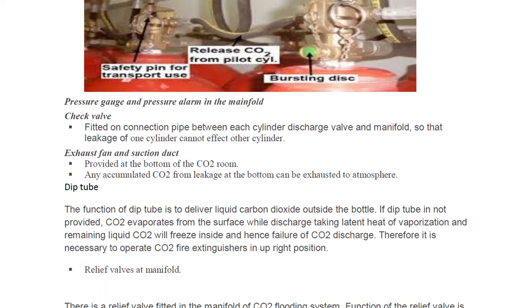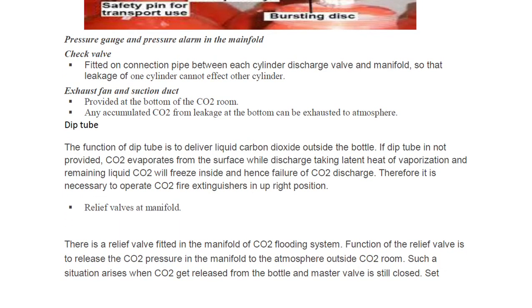We also have a dip tube. The function of a dip tube is to deliver liquid carbon dioxide outside the bottle. It is very important and necessary. If the dip tube is not provided, CO2 evaporates from the surface during discharge, taking the latent heat of vaporization, and the remaining liquid CO2 will freeze inside — causing failure of CO2 discharge.